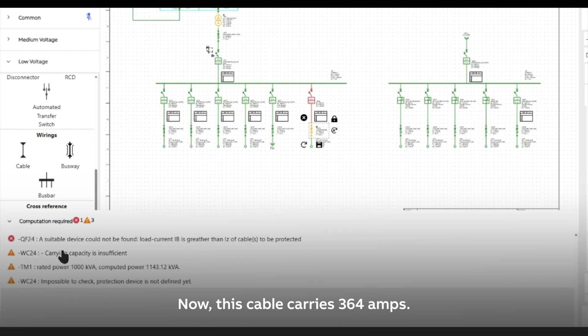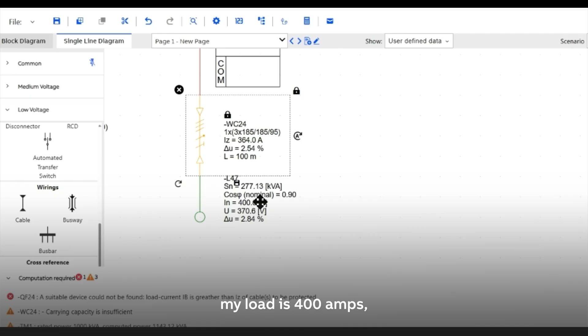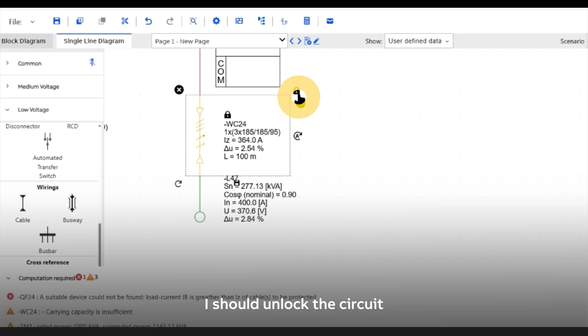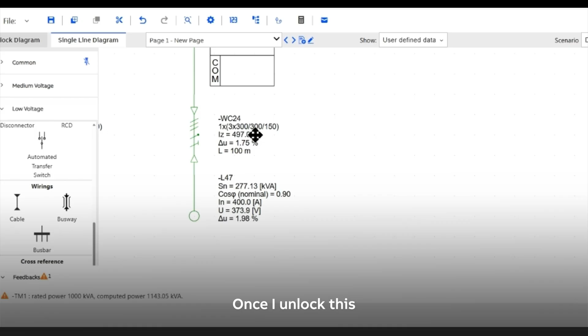Why is this happening? It's because I followed the single line drawing and locked the cable. Now, this cable carries 364 amps. With this installation method, my load is 400 amps, but the cable isn't big enough. To fix this, I should unlock the circuit and run the calculation again to see what cable size is needed. The software suggests using a 300 square millimeter cable. Once I unlock this and run the calculation, the first feedback about the circuit breaker is fixed.